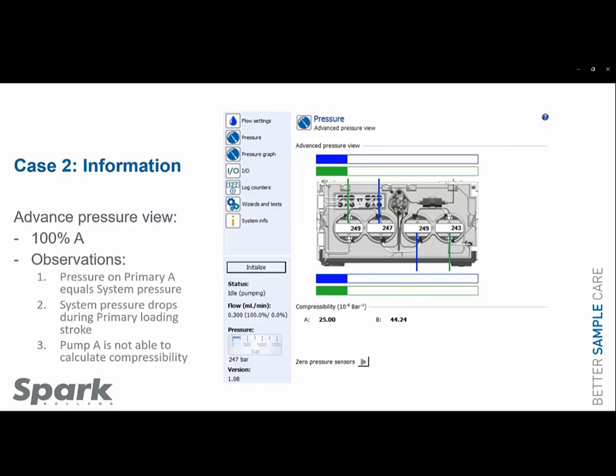Let's see what pump A is doing. So, increasing the pressure. But still, this is strange. This is not good. It's not even calculating compressibility. It cannot, because probably the outlet check valve is continuously open. Yeah, the source of the problem is the outlet check valve. Definitely.